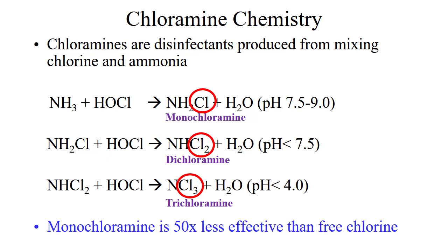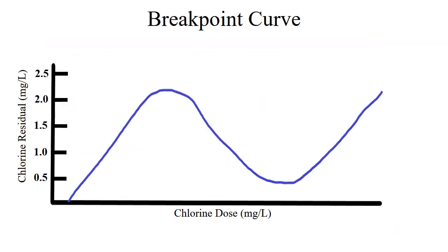Monochloramine is 50 times less effective than a free chlorine residual. This is why the monochloramine residual lasts longer in a distribution system compared to a free chlorine residual and is an effective secondary disinfectant. It is important for any operator working with chloramines to understand the breakpoint curve. Understanding where the plant is on the curve ensures the plant will maintain water quality goals and meet state and federal regulations. The x-axis of the curve is the chlorine dose, or how much chlorine is added to the water. The y-axis is the total chlorine residual. For this video, we made the range from 0 to 2.5 milligrams per liter, but this scale can change based on the target total chlorine residual for the water utility.